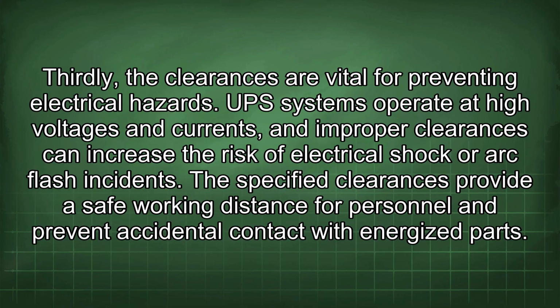Thirdly, the clearances are vital for preventing electrical hazards. UPS systems operate at high voltages and currents, and improper clearances can increase the risk of electrical shock or arc flash incidents. The specified clearances provide a safe working distance for personnel and prevent accidental contact with energized parts.